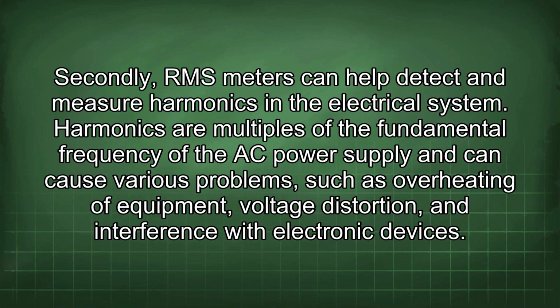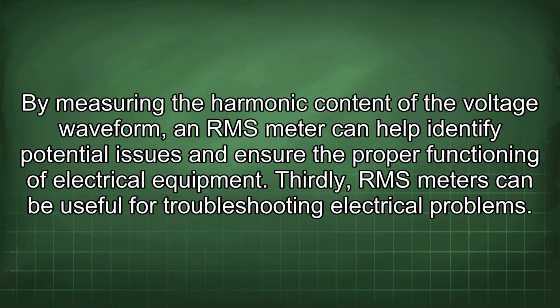Secondly, RMS meters can help detect and measure harmonics in the electrical system. Harmonics are multiples of the fundamental frequency of the AC power supply and can cause various problems, such as overheating of equipment, voltage distortion, and interference with electronic devices. By measuring the harmonic content of the voltage waveform, an RMS meter can help identify potential issues and ensure the proper functioning of electrical equipment.